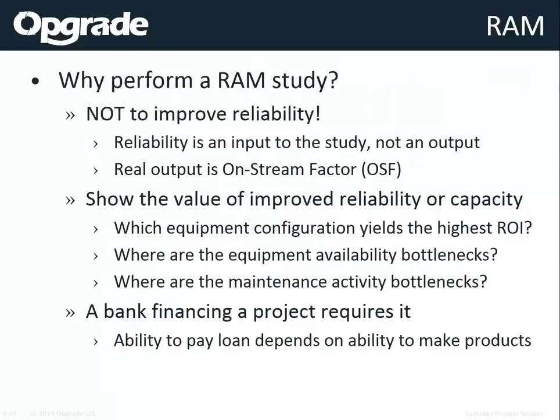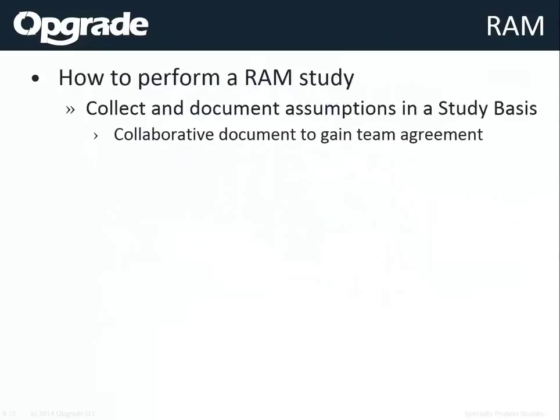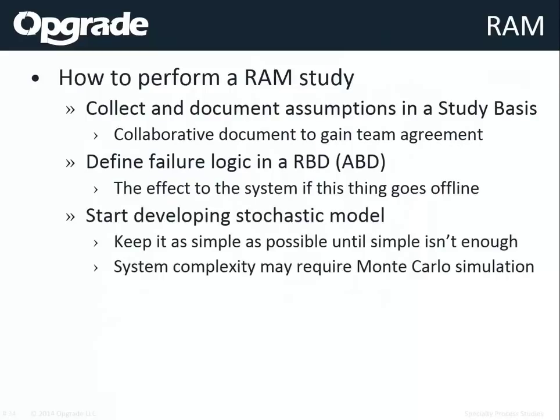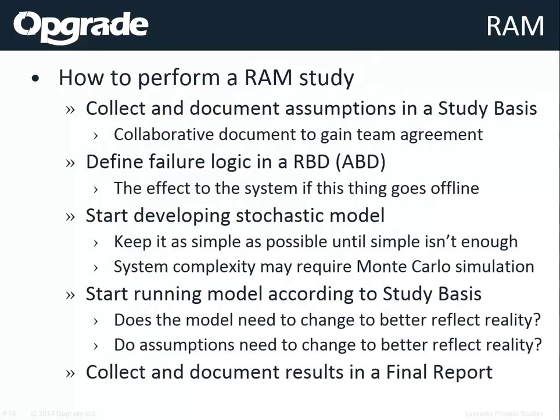We start with a study basis, then define the failure logic in a reliability block diagram — also called an availability block diagram — which shows what happens to the system if a piece of equipment goes offline. We put that into a stochastic model using one of several available software tools. You run the model, identify what needs to change, and iterate in a refinement process until you have a final report.